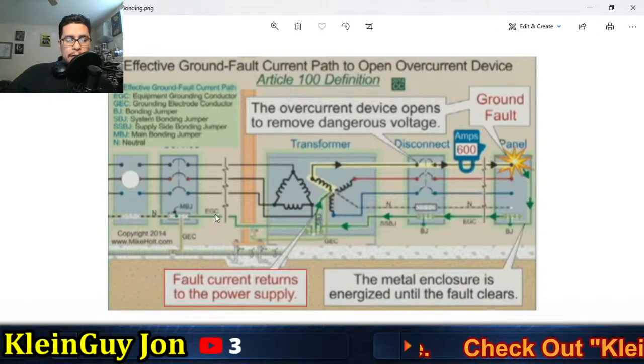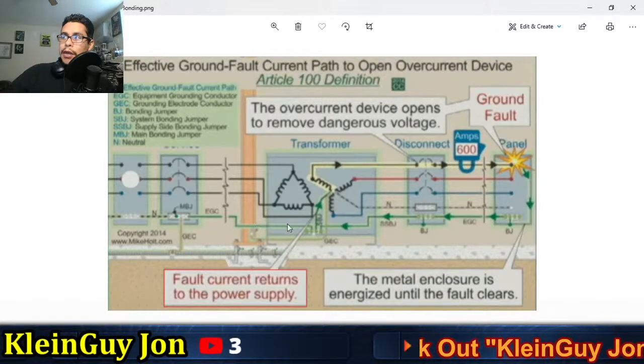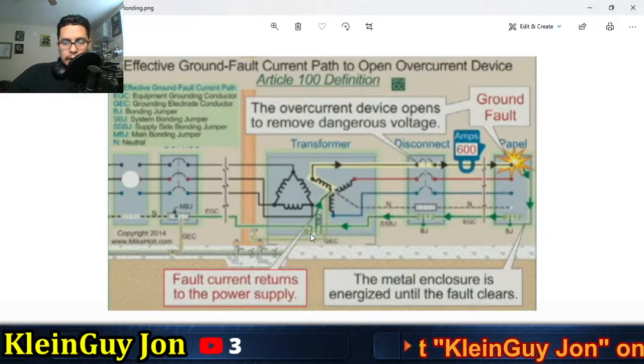Then from that, your equipment grounding conductor, as you see a little green line right here, you follow it, it goes through. Then it hits your terminals here. Now you're into a transformer, so now you have to actually take your grounding electrode conductor and bring it into the X0 terminal, and your X0 is also your neutral. As you see right here, this is your neutral.